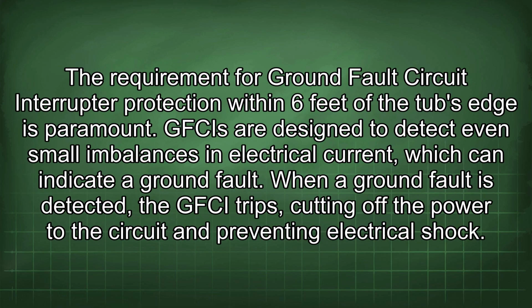The requirement for ground fault circuit interrupter protection within 6 feet of the tub's edge is paramount. GFCIs are designed to detect even small imbalances in electrical current, which can indicate a ground fault. When a ground fault is detected, the GFCI trips, cutting off the power to the circuit and preventing electrical shock.